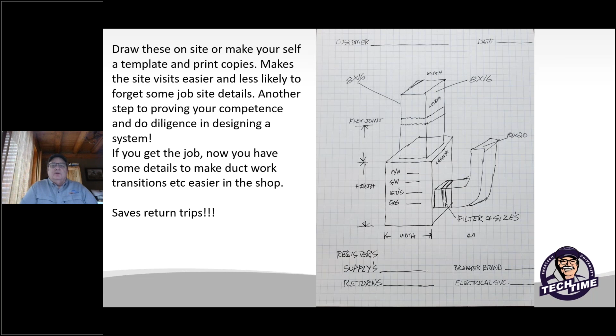So one thing I really look at when I go in and start looking at the ducts, I want to know how many registers and grills there are per floor level. I would actually try to count the numbers off on each individual branch circuit from the plenum. So then I know the ductwork sizing, how much air I can push through each individual trunk. And I think one of the important things is to try to make a system quiet. I always like to try to get somewhere between 90 to 100 CFM per opening, and that may change in your location or your locale. That's kind of an idea of what I used to do. All the notes that you can take, the size of the ductwork, trunk work, all that stuff comes into play and is very important in the end.